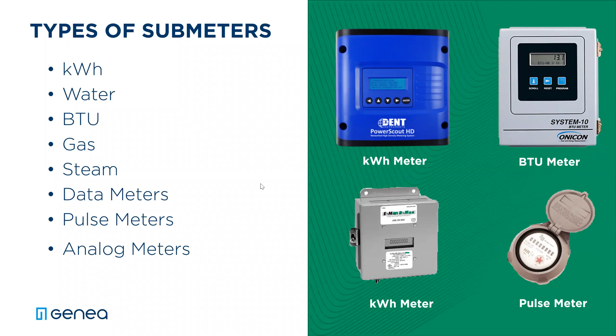The second thing we need to look at is, what type of meter are we going to put in? Different areas of the country tend to like the socket type meters. As you can see here, the Itron is a very common socket meter, seen all over the country. It's really good if you just have a single set of circuits that you want to meter, and you have space in your electrical rooms, because the socket meter and the panel it fits into are generally a little larger than the CT style meters. The socket meter is generally an inline meter as well, so if you have to change it out or remove it, then you will disrupt supply to the tenant.